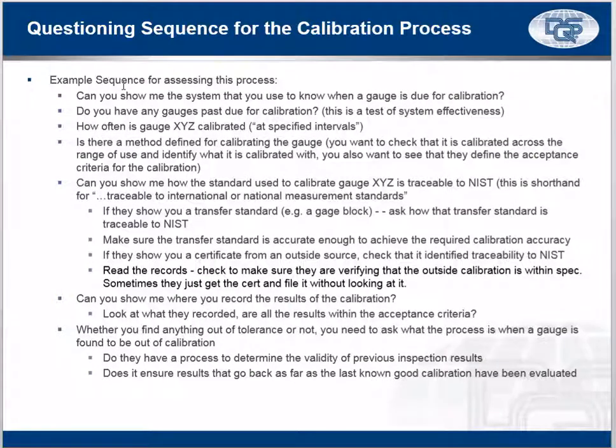Okay, here is a sequence of questioning for getting through the calibration process. I highly recommend you use this sequence. It's time-tested and true. Can you show me the system that you use to know when a gauge is due for calibration? They may show you a spreadsheet. They may show you a gauge tracking program. They've got to show you some sort of monitoring system that enables them to know when something is due.